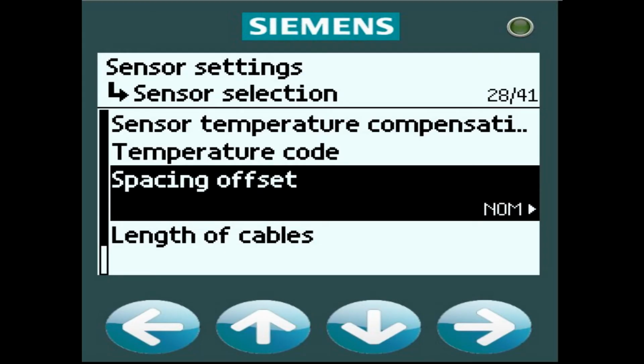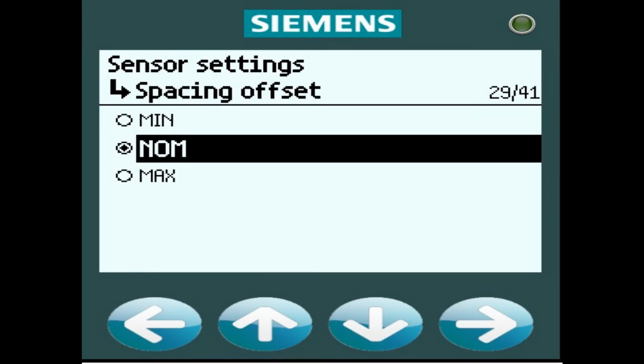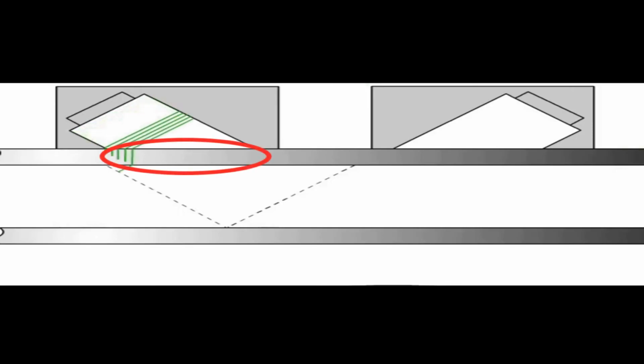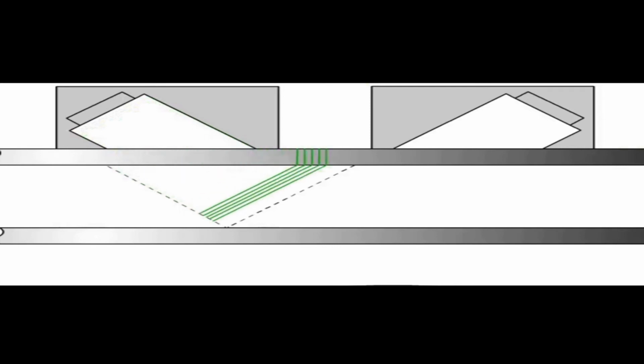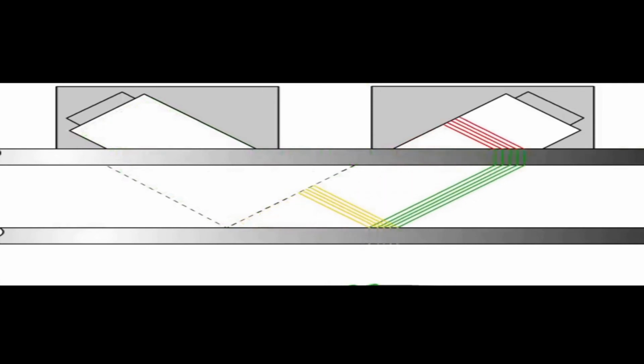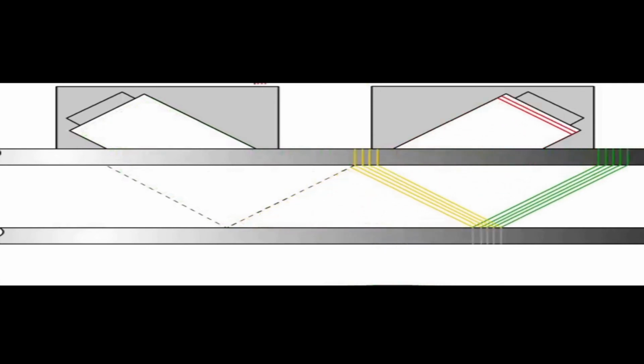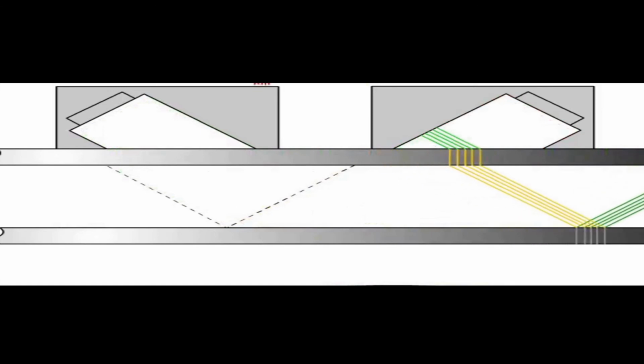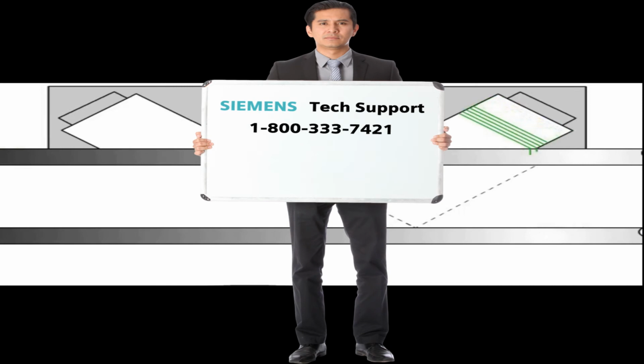And what about that spacing offset? There are 3 possible positions for setting the sensor spacing: minimum, nominal, and maximum. These positions are relative to the number of sonic wavelengths along the pipe. The flowmeter will select the theoretical ideal position based on your application programming. It is generally unnecessary to make any changes. If real-world conditions make it necessary to alter the selection, Siemens Tech Support can guide you through the process.